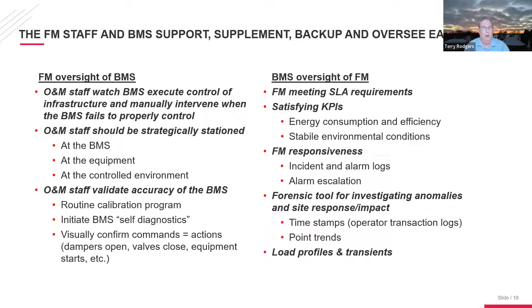So, alarm management: not all alarms should be treated equally. And that's obvious. You could have a benign, almost incidental alarm, and then you can have something like a secondary chill water high temperature, which means that you've lost your chiller plant and you're no longer cooling the load. So all alarms and anomalies should be captured at the front end, at the facility staff, and recorded. Some alarms need to be distributed through remote annunciation, through cell phone or text pagers, whatever, to your roving staff.